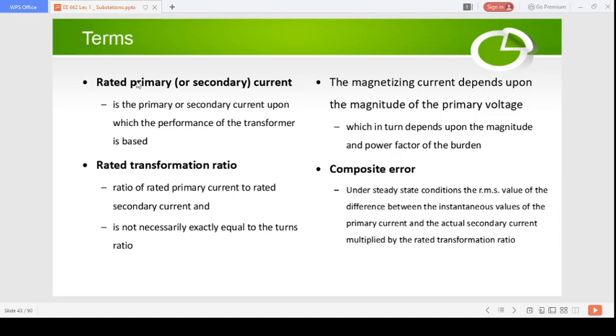Okay, so we will take a look at some terms related to these current transformers and potential transformers, what we call the CTs and PTs. The first term is rated primary or secondary current, for the current transformers. This is the primary or secondary current upon which the performance of the transformer is based. The primary is the current in the bus bar or the lines, and the secondary current is the current at the measurement site.